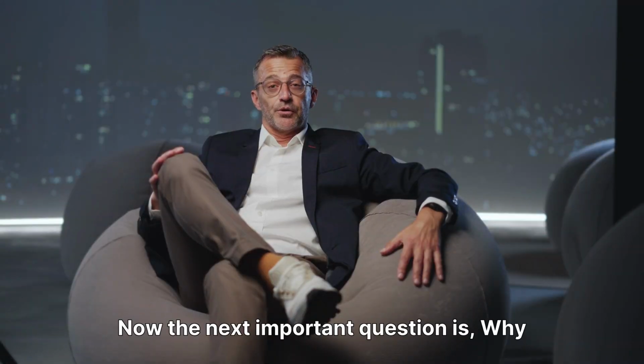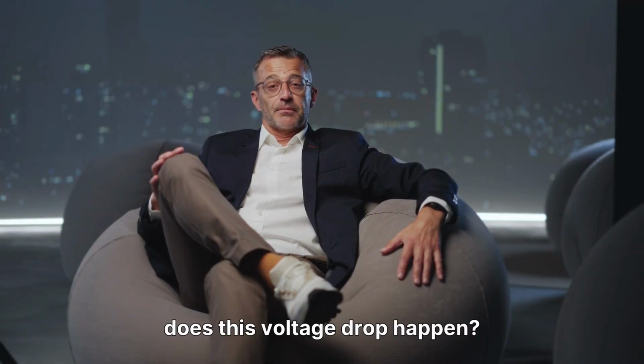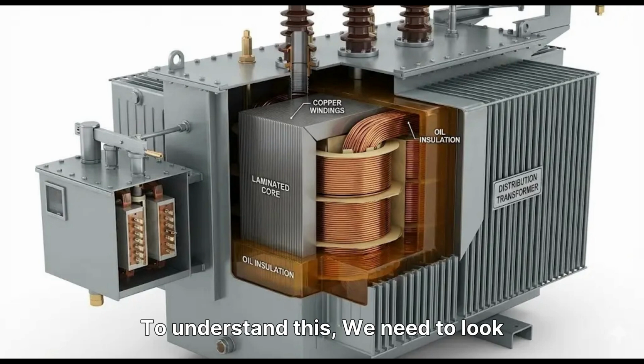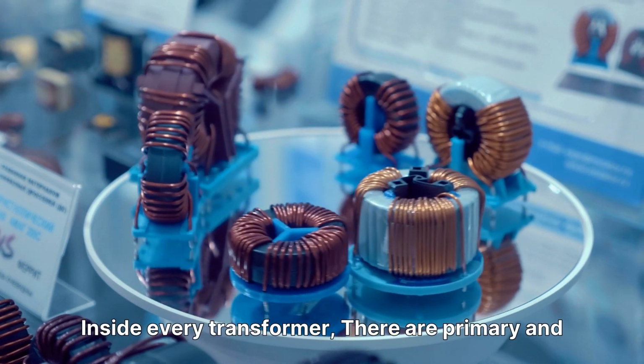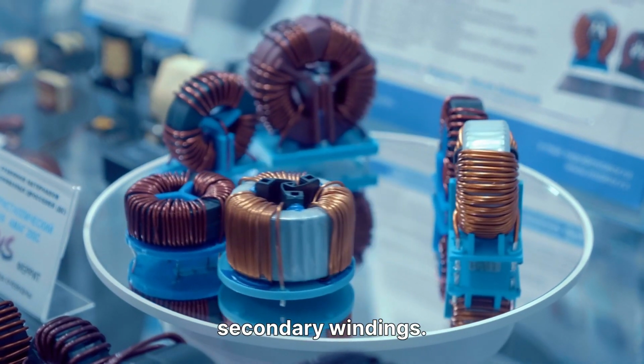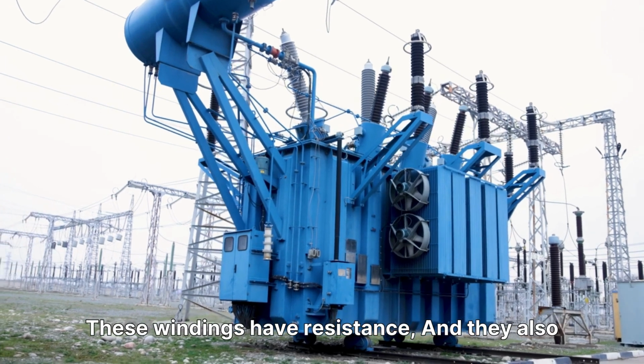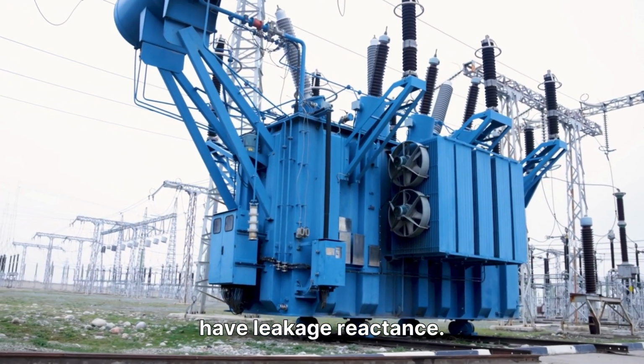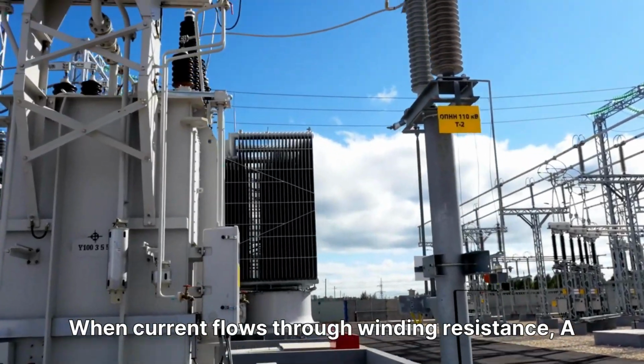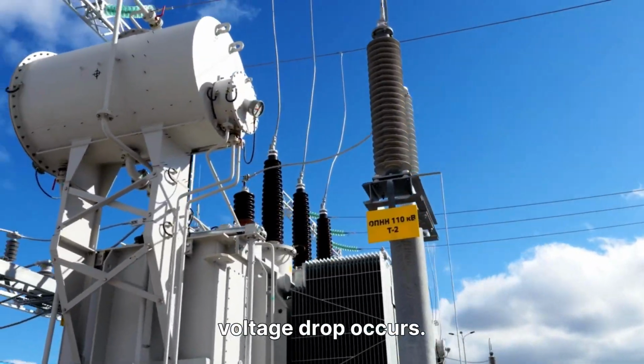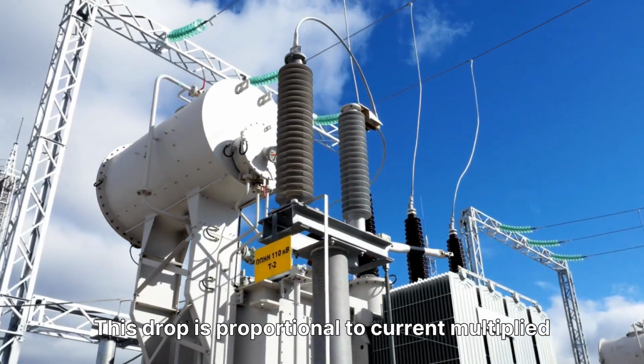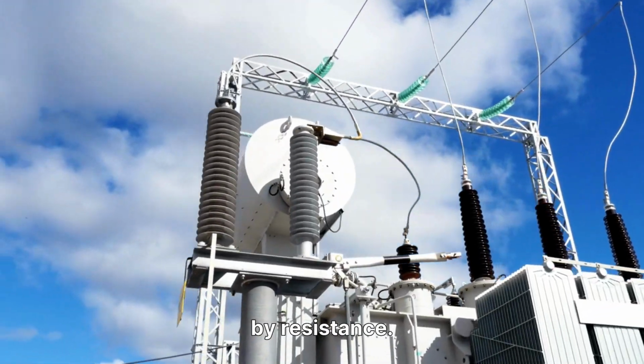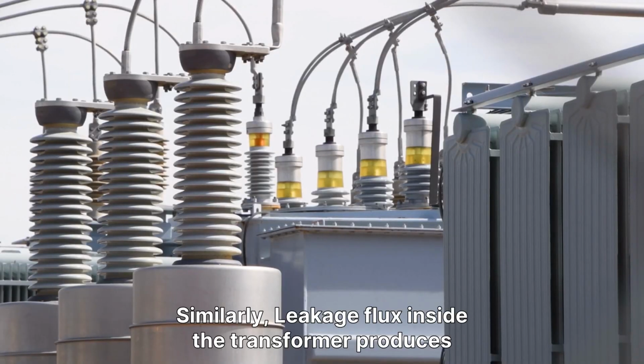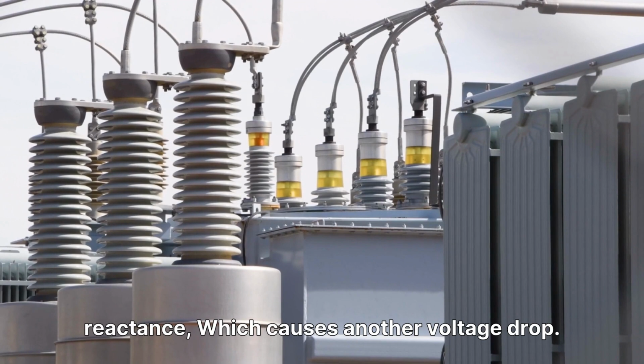Now the next important question is, why does this voltage drop happen? To understand this, we need to look inside the transformer. Inside every transformer, there are primary and secondary windings. These windings have resistance, and they also have leakage reactance. When current flows through winding resistance, a voltage drop occurs. This drop is proportional to current multiplied by resistance. Similarly, leakage flux inside the transformer produces reactance, which causes another voltage drop.